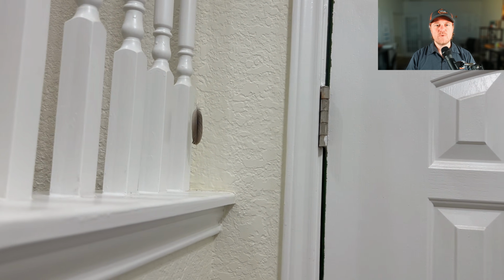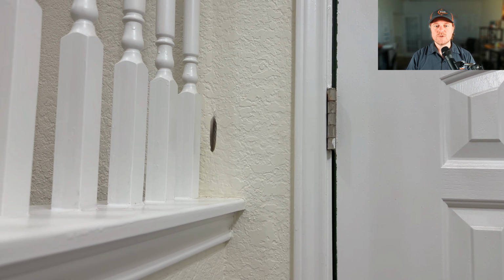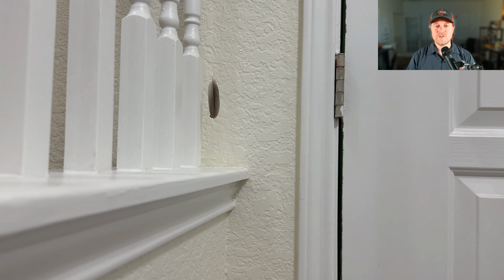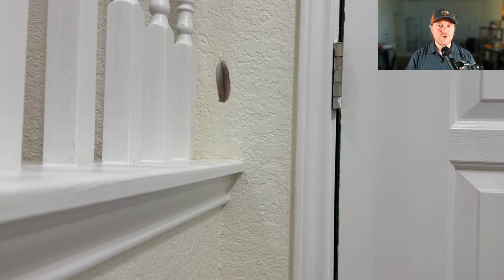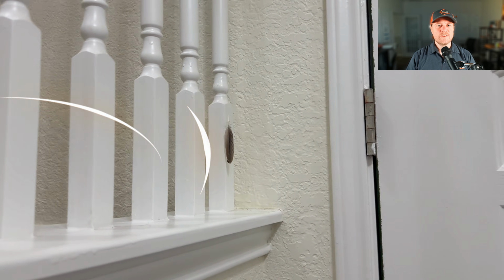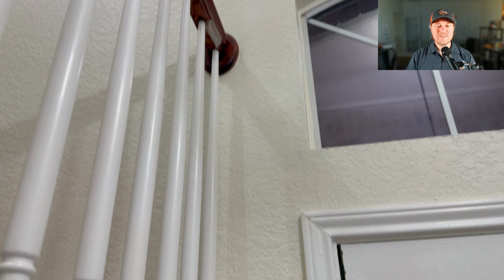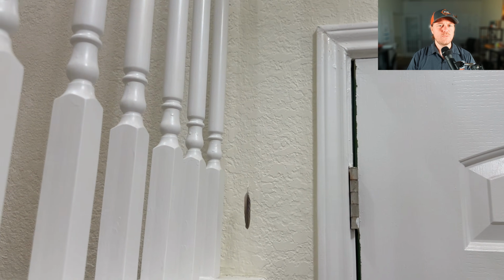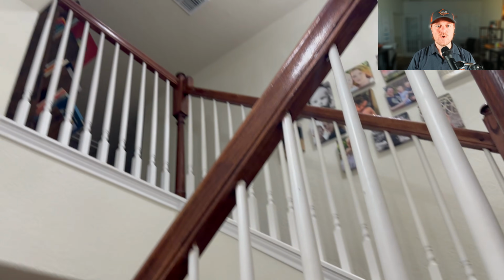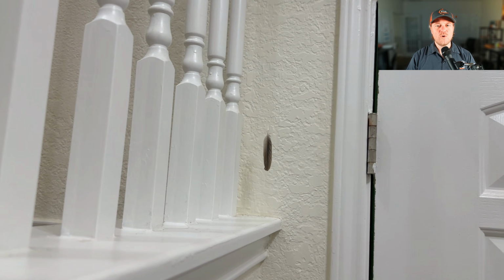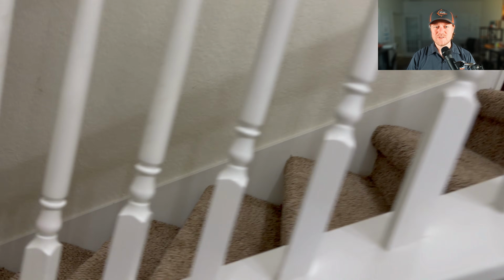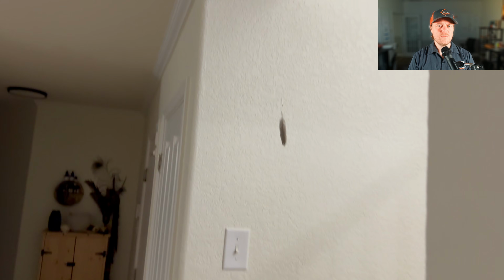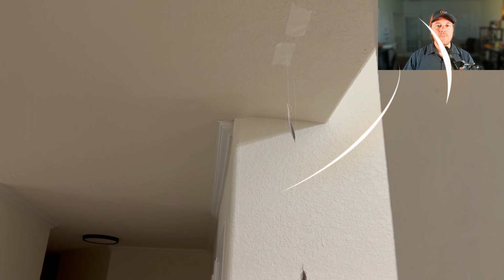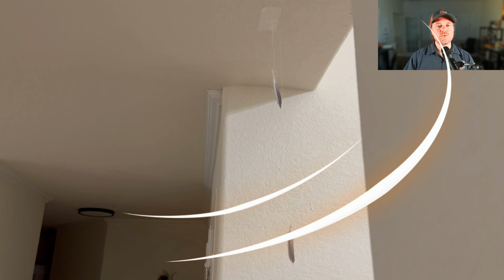The kids found a couple dove feathers outside. I tied them to a string, and then for this one I taped it to the handrail just to capture what the air is doing. What's happening here is as the vent above the stairwell is pushing air, it's hitting this back wall. Then from there, it's pushing its way over the side of the stairwell. And since cooler air ends up being a little bit heavier than warmer air, it's then falling to the ground and spreading out downstairs. And the return air is being pulled right below the ceiling of the downstairs, making its way up to the 18-inch return upstairs.